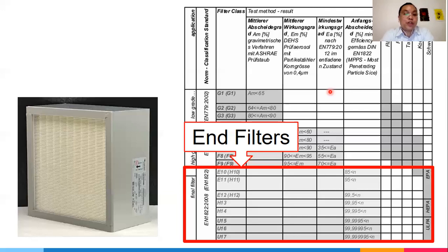But if you put your HEPA filters at your terminal unit, that's not considered by the manufacturer, not by Daikin, Trane, or Carrier. You have to tell them, specify, or add the pressure drop of your HEPA filter to the external static pressure requirement of your fan.